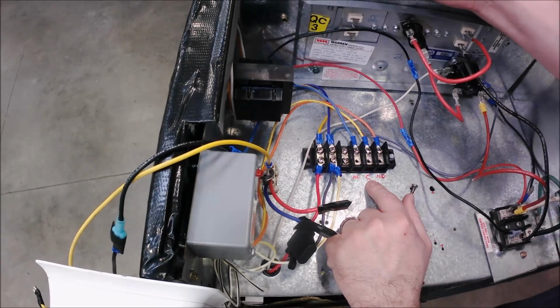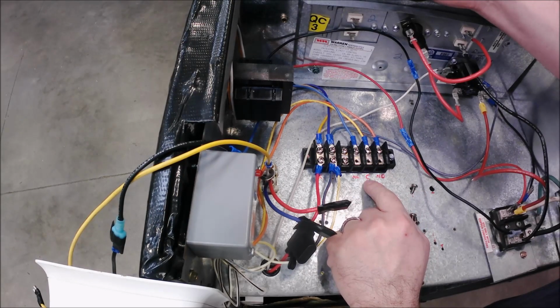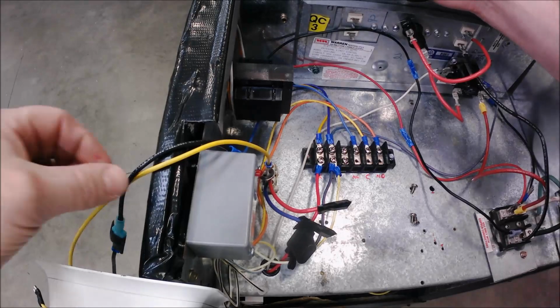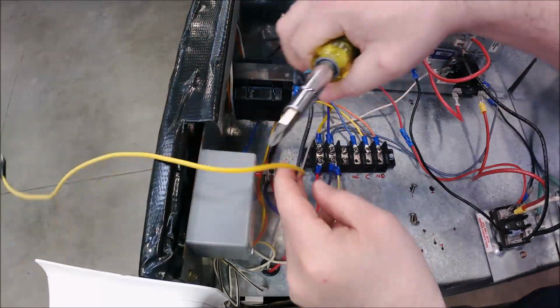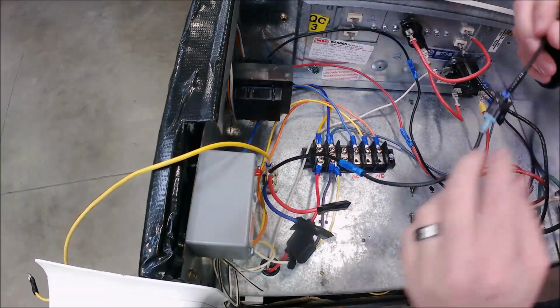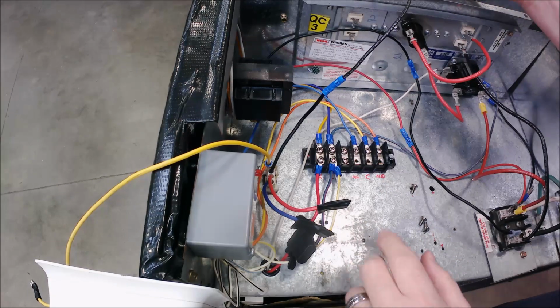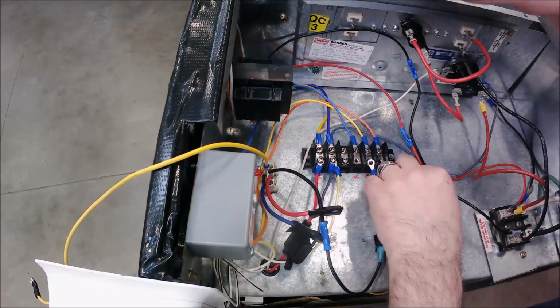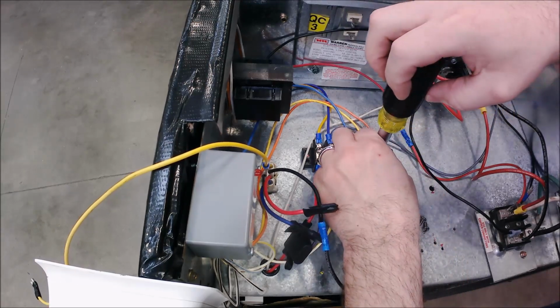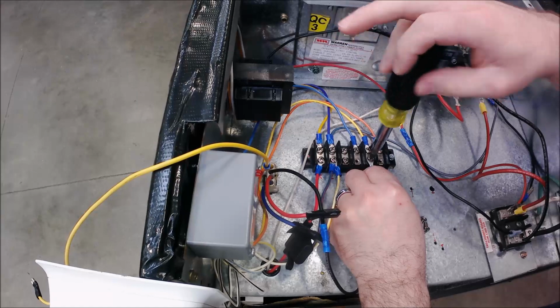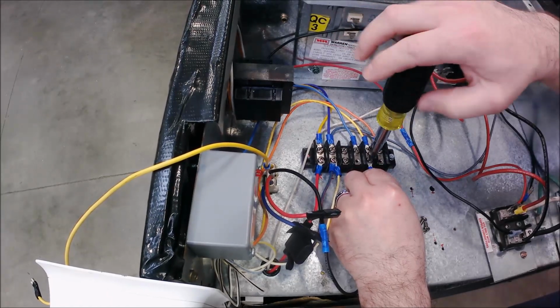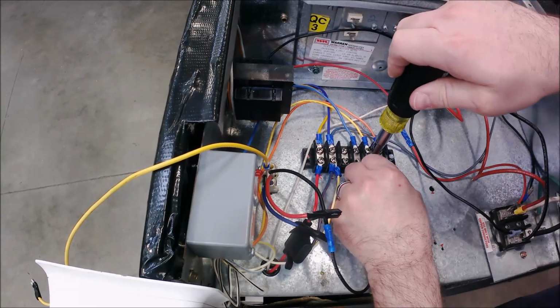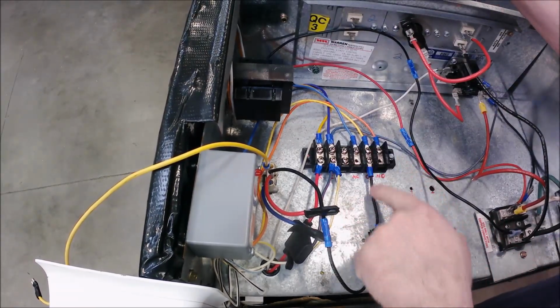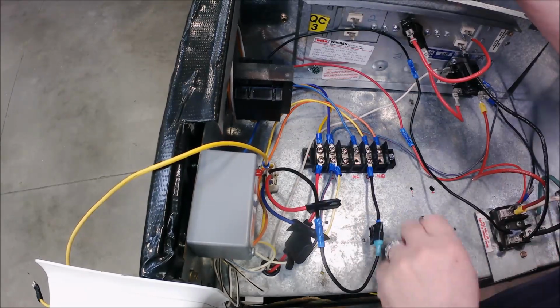This common right here is basically, no matter if we're using the normally closed or the normally open relay, we're getting power out of that terminal, right, out of that wire. So what I'm going to do here is I'm going to put my PSC motor, I'm going to put my speed on that common. Now I've got my red and blue, and this is black, okay? So whatever speed you're using, the way most manufacturers are probably going to, like I said, residential wise, if you see this setup, we're going to have a multi-speed PSC motor, but we're only going to use one speed for heat or cool. That's exactly what Goodman does with theirs. So that is going to go, and I can change right here. I can change the speeds if I need to adjust the CFM.